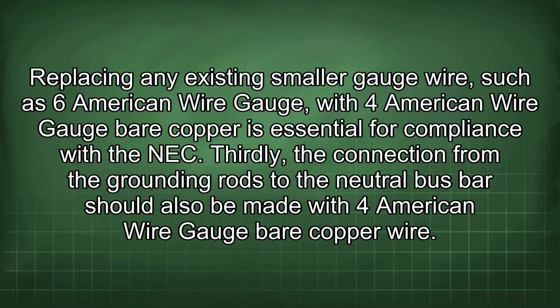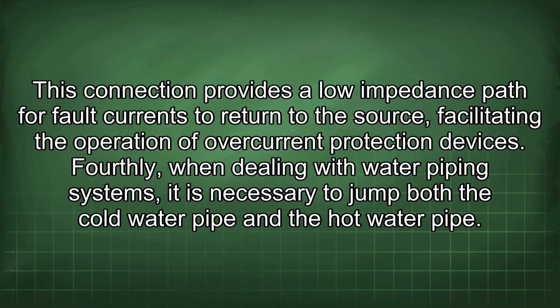Thirdly, the connection from the grounding rods to the neutral bus bar should also be made with 4 American wire gauge bare copper wire. This connection provides a low impedance path for fault currents to return to the source, facilitating the operation of overcurrent protection devices.